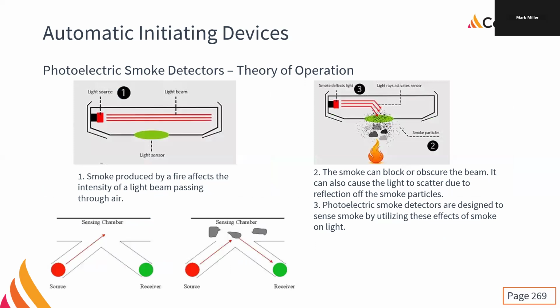Photoelectric smoke detectors. We have a light source and a light sensor, right? If we throw light into the chamber and it doesn't come back, everything is good. If we throw light into the chamber and it reflects off of the smoke and hits the receiver, then we have smoke. So we have a fire. So that's how it works.